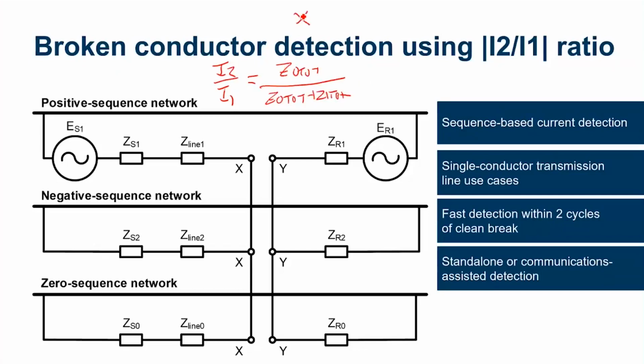Now, if we use the rule of thumb that Z0 equals 3Z1, then for a broken conductor I2 over I1 should equal 3/4, or 0.75. That's in an ideal condition. However, your zero sequence sources aren't always 100% known. Your zero sequence can change based on the soil resistivity and the moisture in the soil, so that's going to change over time and throughout the year. Other things that can change are your zero sequence sources. If you've got, for example, a delta-Y transformer in your network, that's going to cut off part of your zero sequence network, and that's going to reduce your Z0 total, making this overall number go down.